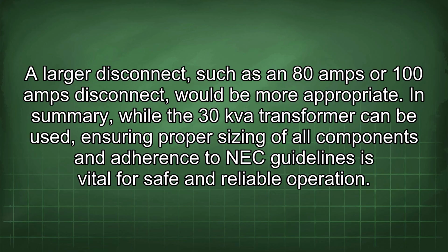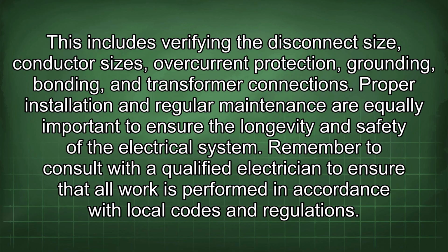In summary, while the 30 kVA transformer can be used, ensuring proper sizing of all components and adherence to NEC guidelines is vital for safe and reliable operation. This includes verifying the disconnect size, conductor sizes, overcurrent protection, grounding, bonding, and transformer connections. Proper installation and regular maintenance are equally important to ensure the longevity and safety of the electrical system. Remember to consult with a qualified electrician to ensure that all work is performed in accordance with local codes and regulations.